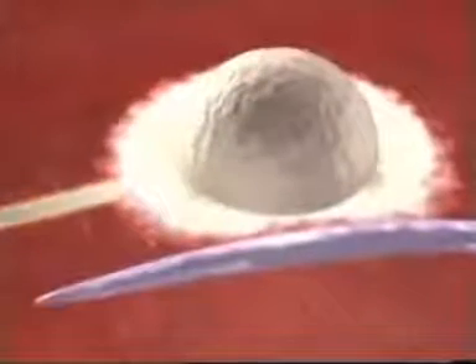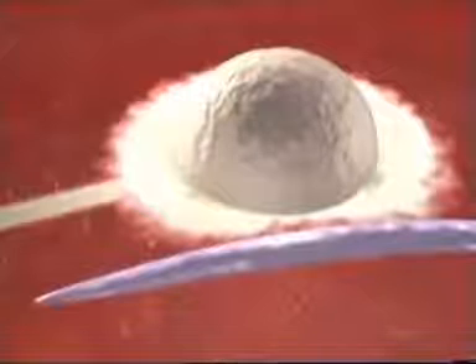Once an ablation or series of ablations is completed, the track along which the device travels can be ablated. Physicians generally choose to ablate the track in order to prevent potential seeding and to control any potential bleeding. If using the Starburst 3 centimeter device, you would watch the number 4 thermocouple during track ablation.